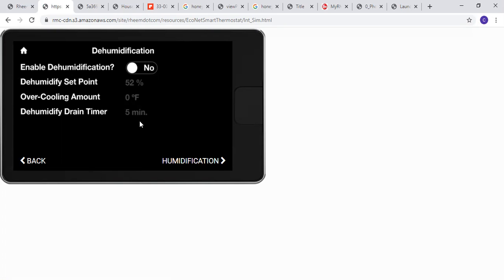So what's that is designed, that can be increased quite a bit actually. Basically at the end of every cycle, your blower is going to turn off for 5 minutes. There again, you can increase this to 7, 10, 15, whatever you want to. The purpose behind this is those new coils, they're so much bigger, they're so much denser. So once the cooling cycle is over, it holds quite a bit of water.